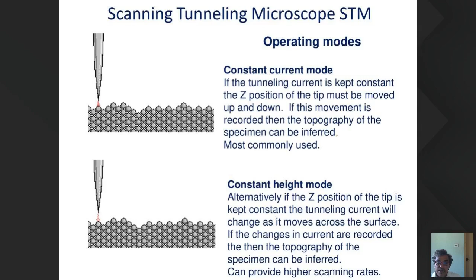Alternatively, the position of the tip is kept constant. That means you are going to maintain the height. The tunneling current will change as it moves across the surface, because of the varying distance between the tip and the specimen surface. The changes in current are recorded, and then the topography of the specimen can be inferred. This can provide a higher scanning rate compared to the constant current mode.